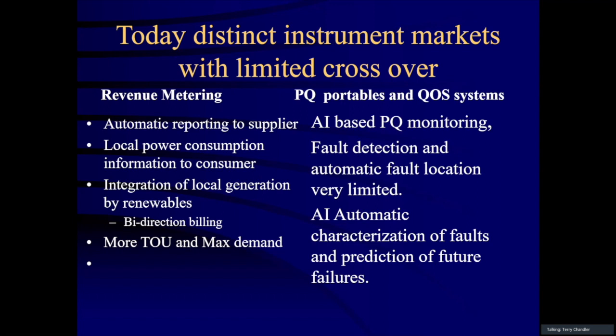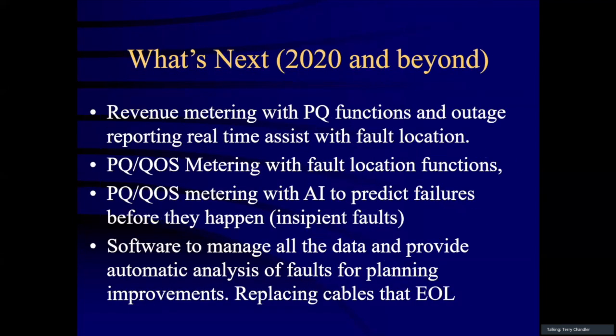So fault detection, automatic fault location, and then involving artificial intelligence, we're now seeing automatic characterization of faults and prediction of future failures. So what's coming next? Revenue metering with PQ functions and outage reporting, real-time assistance with fault location. If every residence had a revenue meter that could send a message to the utility when a fault occurred, they would know very quickly where the fault was located.